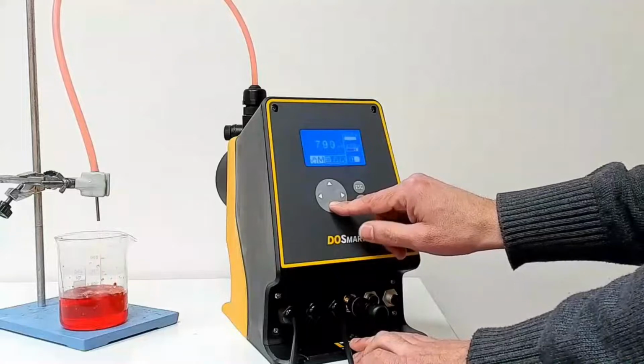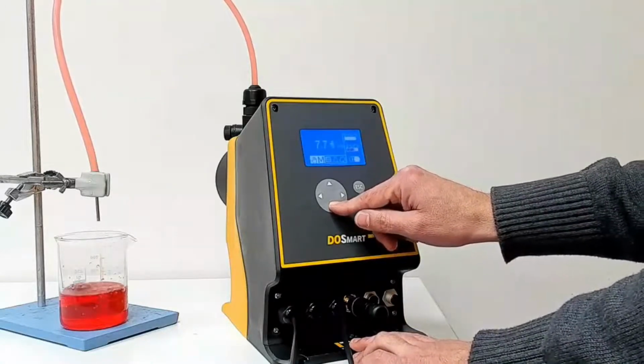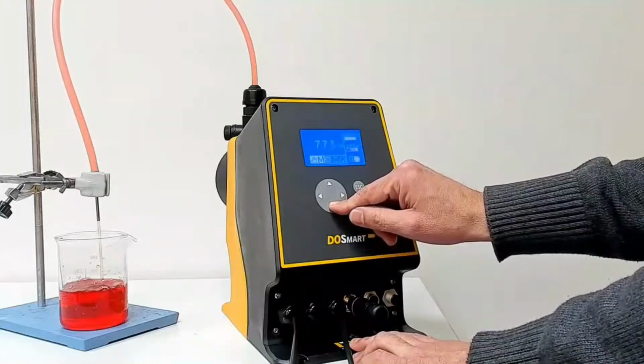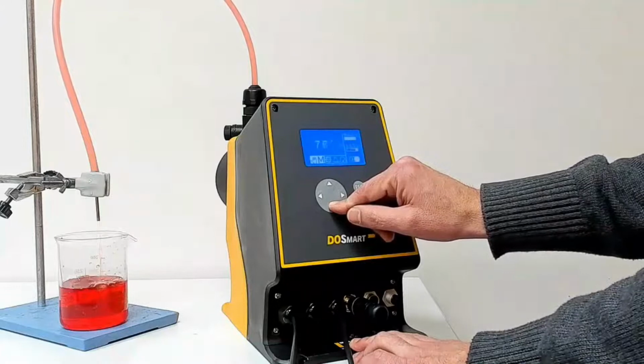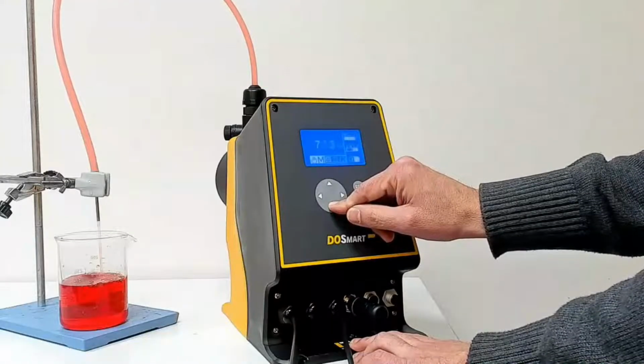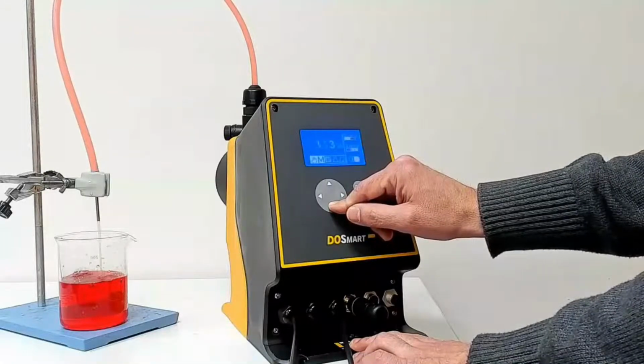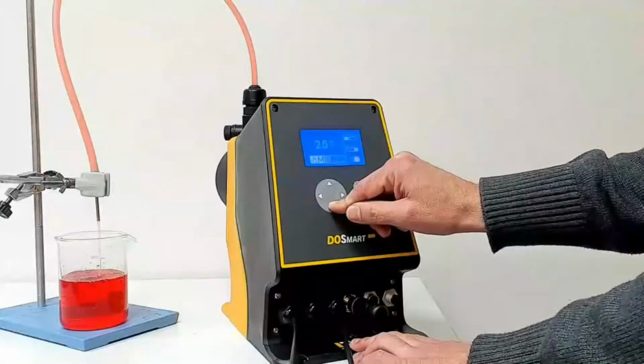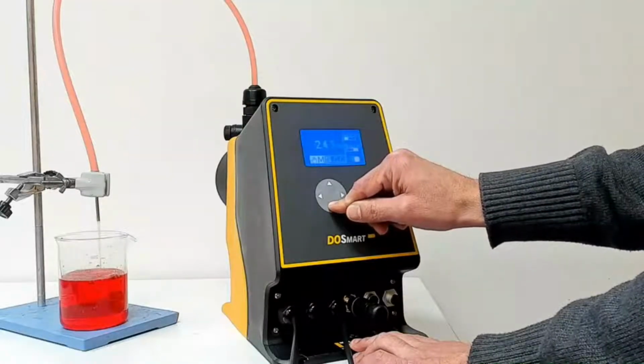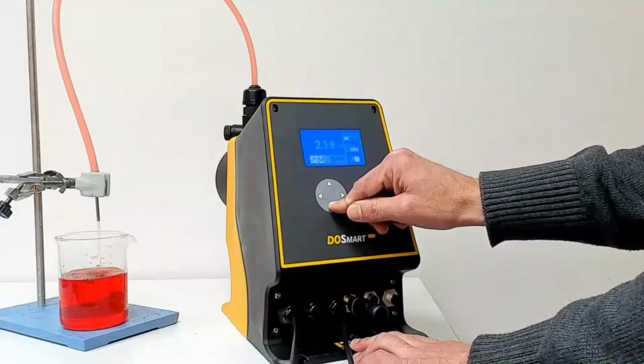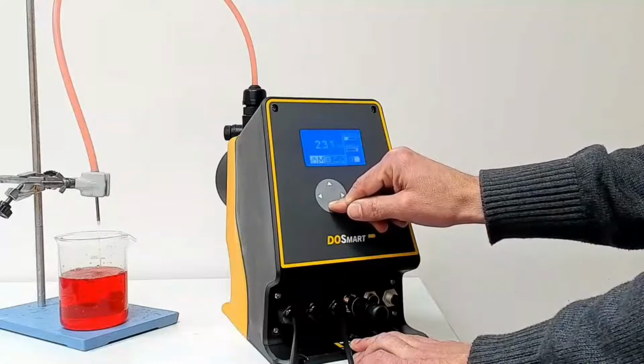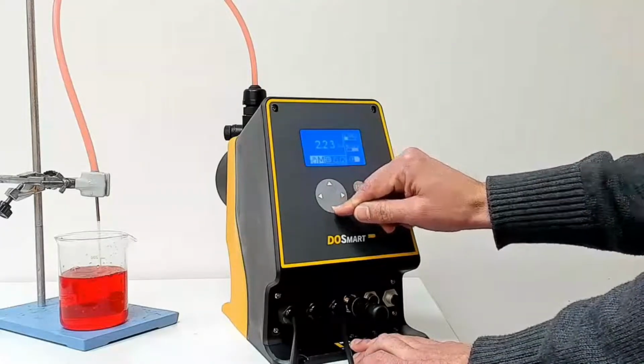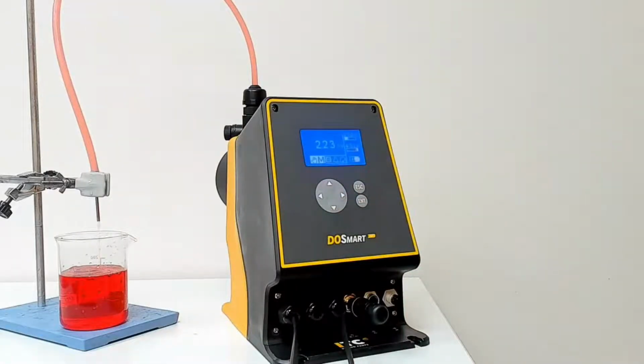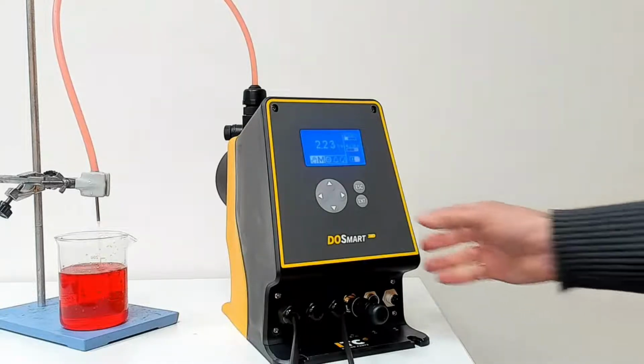One of the most important points of that pump is the low pulsation on the delivery of the product. At the time that we reduce the flow, the suction cycle remains stable, with no change, but we are taking longer time for the delivery cycle. By doing this, we reduce the gap between two cycles, the gap between two injections. So the space of time with no product injected is being reduced a lot. This is the reason that we call it low pulsated flow. Actually, you see the short time in suction and the long time in the discharge of the product.